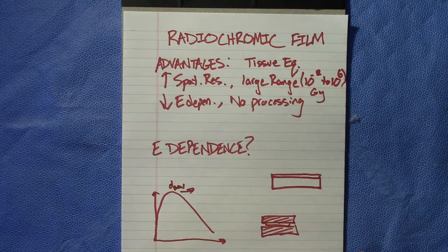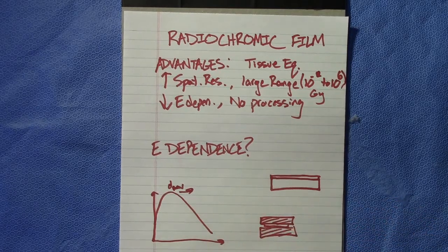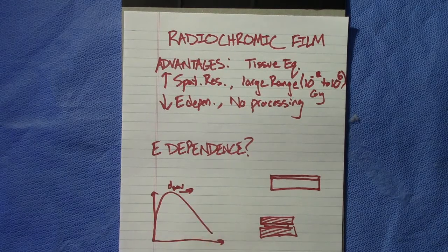By putting it past Dmax, not only are you now in transient charged particle equilibrium, but in the buildup region and at Dmax, the slope varies quite a bit. A very small error in setup could result in a big dose distribution change and impede your results and making them look good. And so be sure that it is past the buildup region when you are shooting the film.